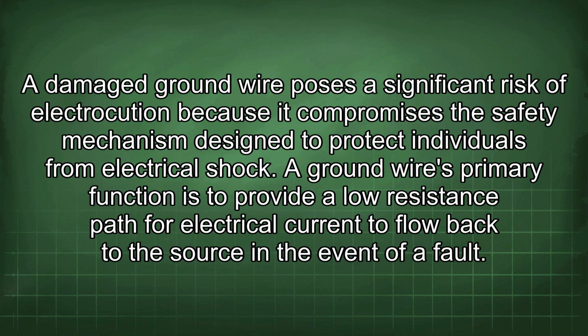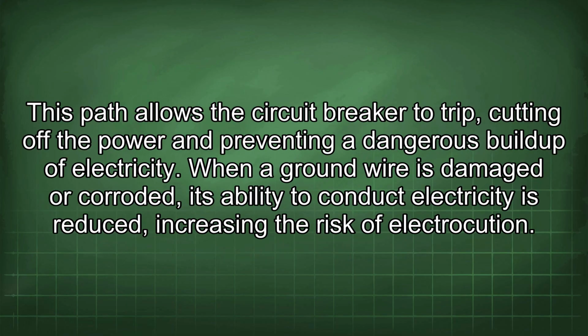A damaged ground wire poses a significant risk of electrocution because it compromises the safety mechanism designed to protect individuals from electrical shock. A ground wire's primary function is to provide a low-resistance path for electrical current to flow back to the source in the event of a fault. This path allows the circuit breaker to trip, cutting off the power and preventing a dangerous buildup of electricity. When a ground wire is damaged or corroded, its ability to conduct electricity is reduced, increasing the risk of electrocution.